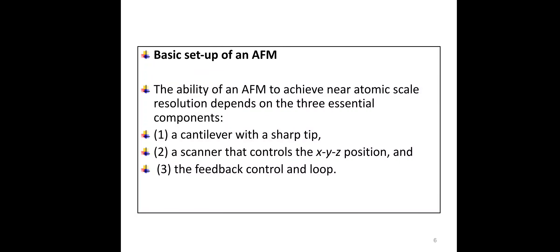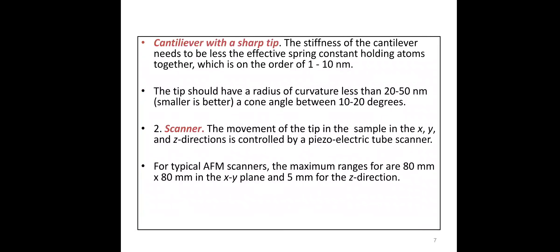AFM achieves atomic scale resolution. We use a cantilever with a sharp tip. It also has a scanner that controls the XYZ position and a feedback control loop. The cantilever needs to have a low effective spring constant, with a tip of the order of 1 to 10 nanometers in diameter. The tip should have a radius of curvature less than 20 to 50 nanometers.